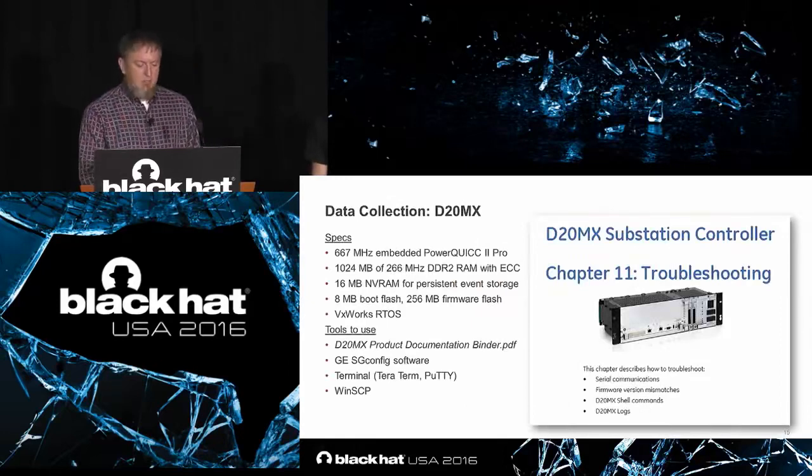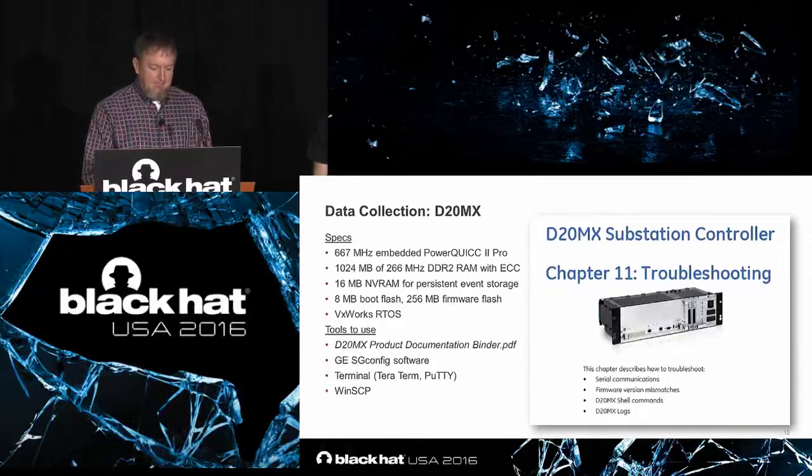PowerQUICC II Pro processor on this D20. It's got a gig of RAM. It's got VxWorks. If any of you are familiar with the substation world, you're probably familiar with this device and you probably have these manuals already. So this is for you, some information that you can use in case you need to do some forensics, even if it's troubleshooting an actual configuration problem.